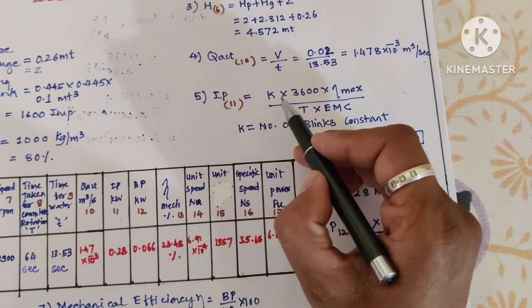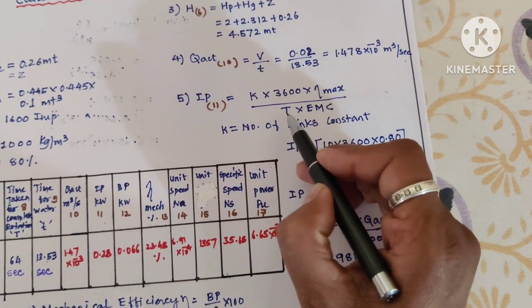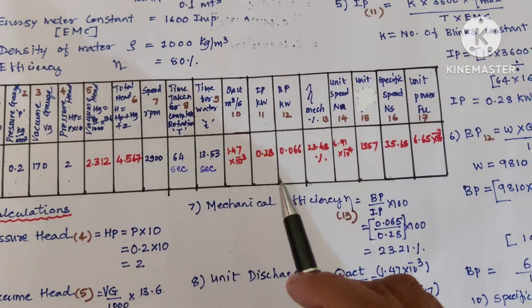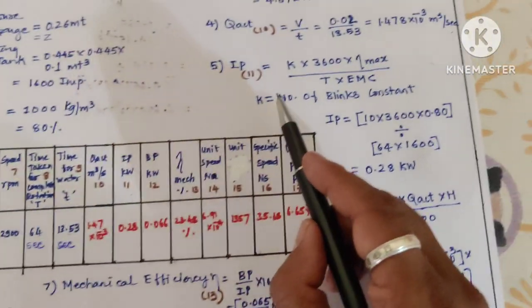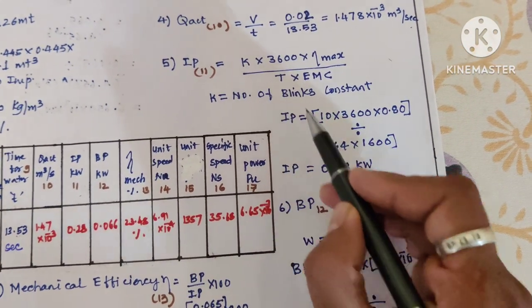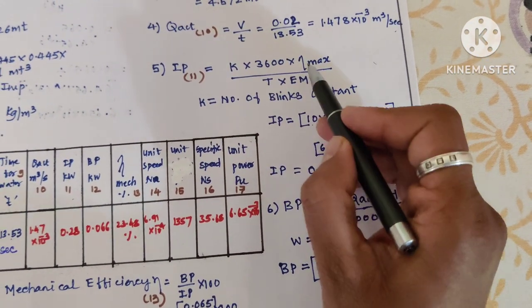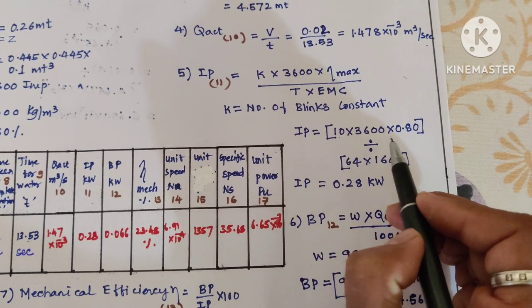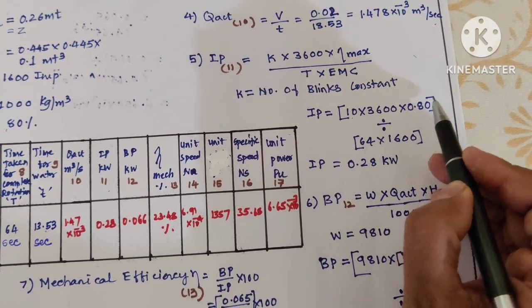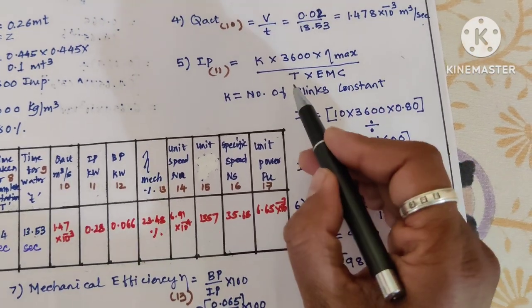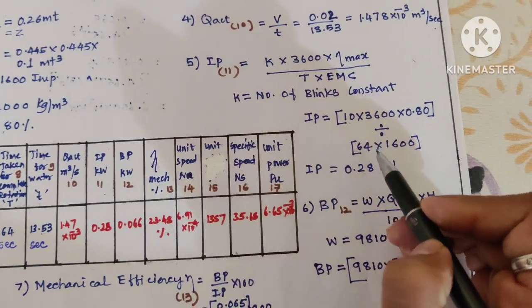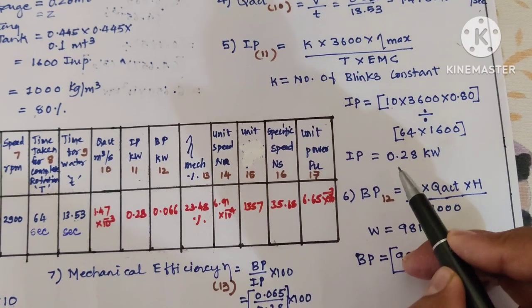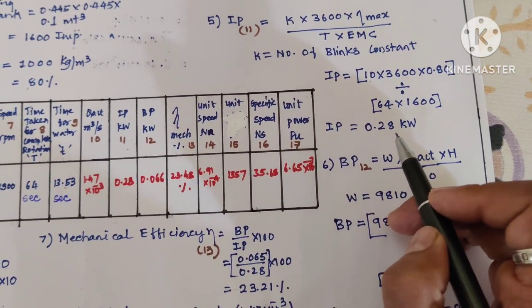Next we will go for IP. The formula is k × 3600 × efficiency / (T × EMC). K is the number of blinks, which is 10. 3600, efficiency is 80% but I'm writing 0.80. Divided by T (64 seconds) into 1600, which is the energy meter constant. We get indicated power as 0.28 kilowatt.